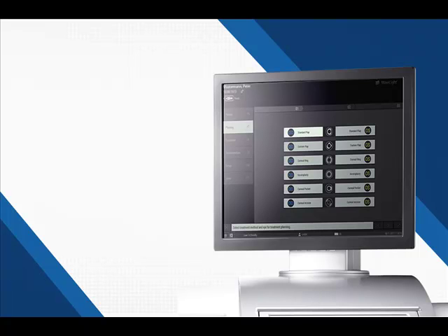So what else, slide 21, what else can cause challenges, difficulties, if we don't think about them and plan before we start? Patient head misalignment, gurney or the surgical bed misalignment, the metallic lid speculum, the device that goes in the eye to open the eyelids. The patient interface might bump into it. So we have to make sure that the eye is opened enough and we have enough clearance that the silicone skirt does not hit onto the metal speculum.